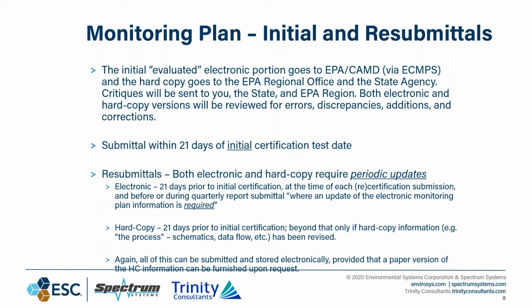Any critiques, any comments, observations get sent to you, the state, and your region. Both portions of the monitoring plan get reviewed for errors, for discrepancies, for anything that needs to get added or corrected. Now, the hard date on that is that submittal needs to occur within 21 days of your initial certification test date.